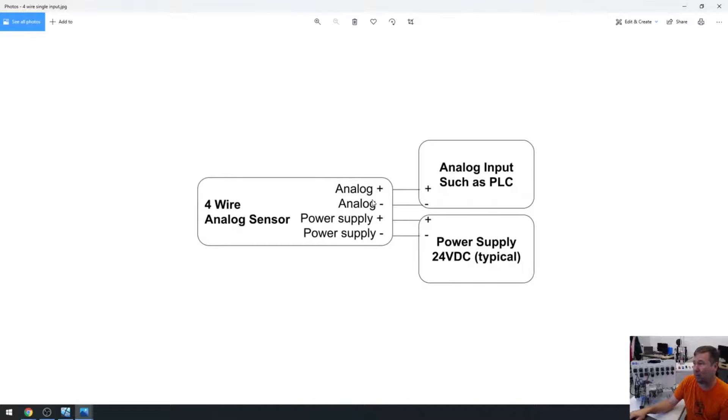Also, you have a three wire device. And on a three wire device, the analog minus and the power supply minus will be internally jumpered. So a three wire device will be wired typically like a four wire device.